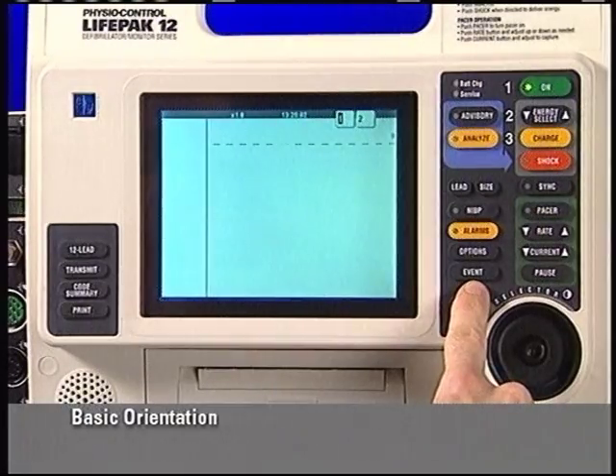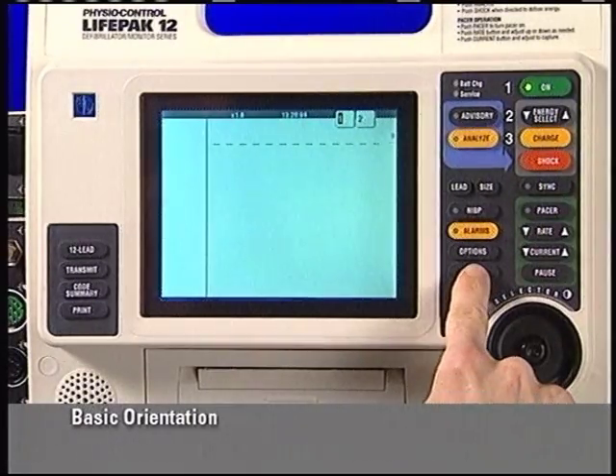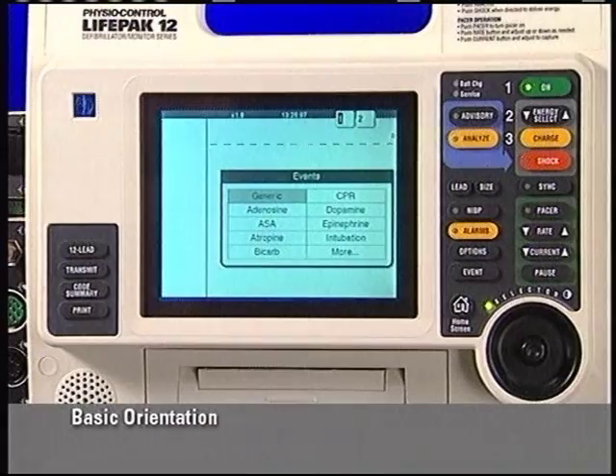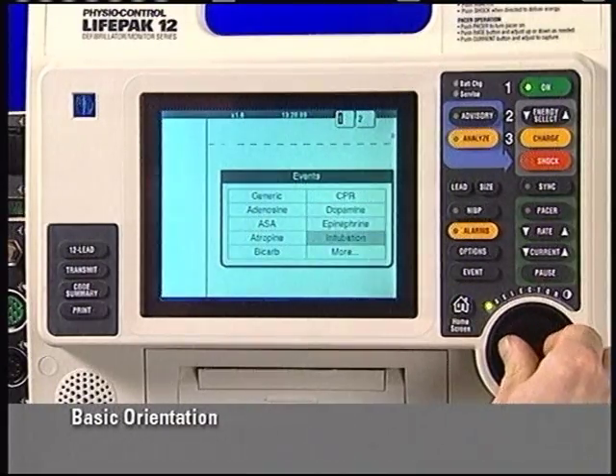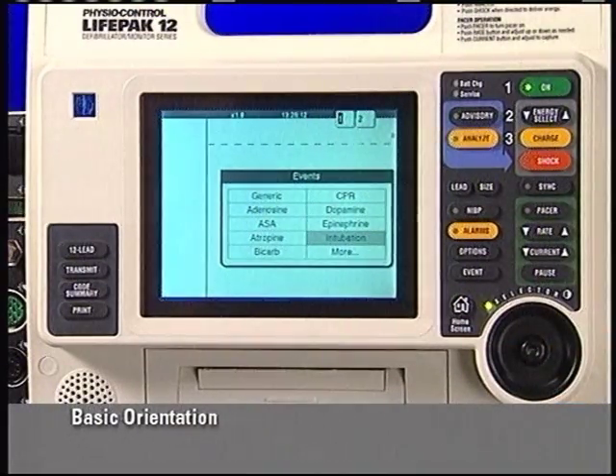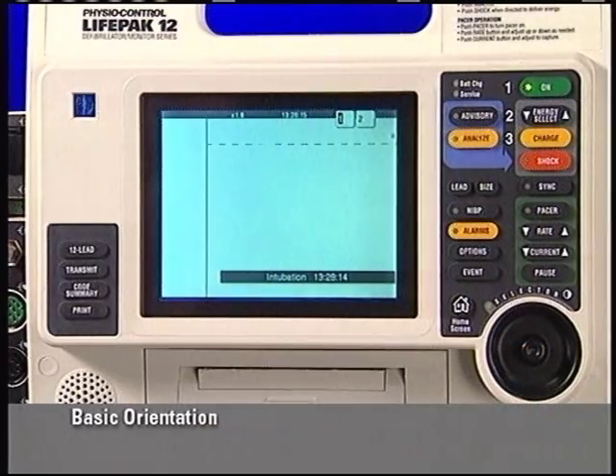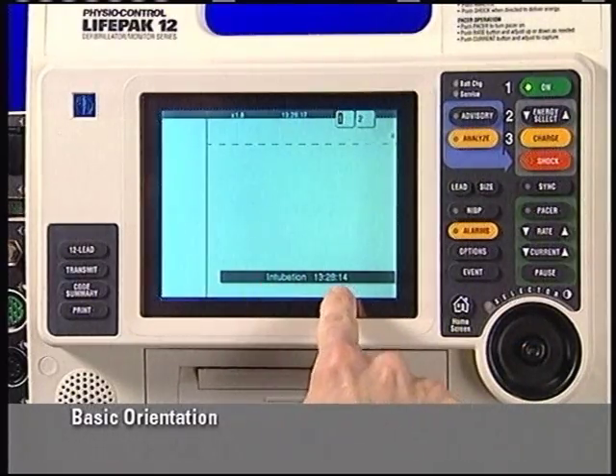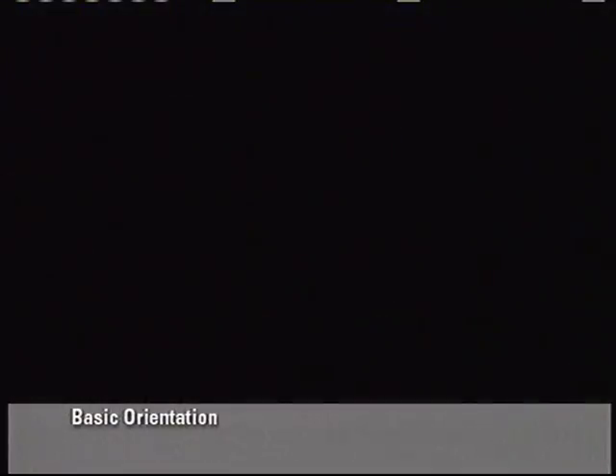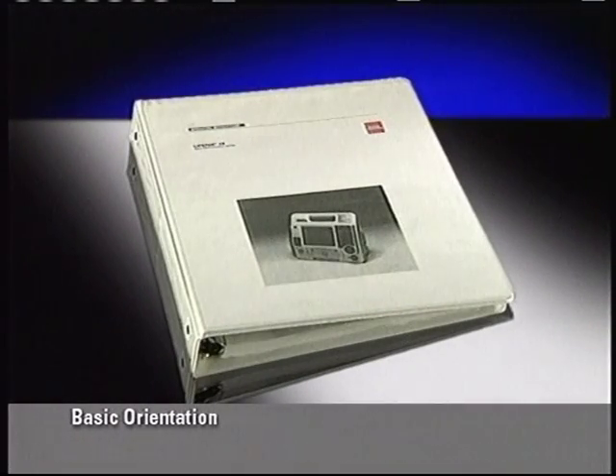The Event button allows you to annotate events on the Code Summary Event log. Press Event to access the event menu. Rotate the selector to highlight the desired event. Note that the highlight is gray. Press the selector. This selects the event, which becomes black highlighted, and appears with a timestamp in the lower area of the screen. For information about defining events for your LifePak 12 defibrillator monitor, refer to Defining Setup Options in the Operating Instruction Manual.